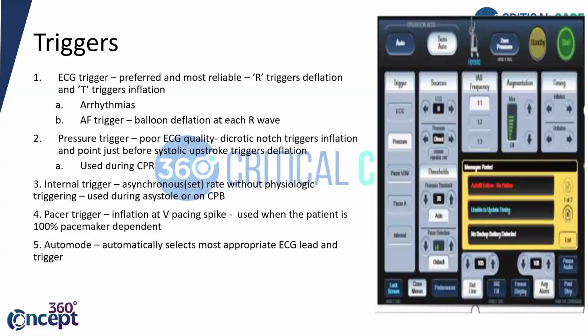So next, coming to the next commonly used trigger, the pressure trigger, whenever there is poor ECG quality. So you did a lot of things, so this patient has some subcutaneous emphysema because of which your ECG quality is not great, or there is some pericardial collection which is leading to poor ECG quality. Then you have no other choice. Then you can put an arterial line and you can trigger it to the dicrotic notch on the pressure waveform, which I've already discussed. So you can use the dicrotic notch for triggering the inflation, and at the point just before the systolic upstroke, there will be deflation. So it is best used during your CPR. So when you are doing CPR, we know you'll not have any electrical activity. So from the arterial line, it will pick up the arterial trace and it will time your IABP inflation.